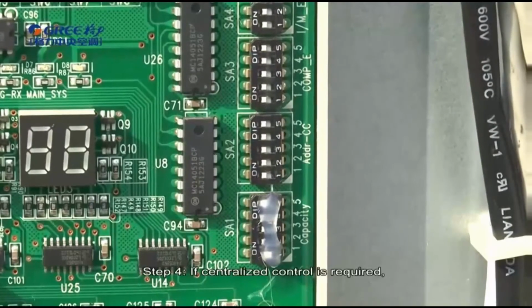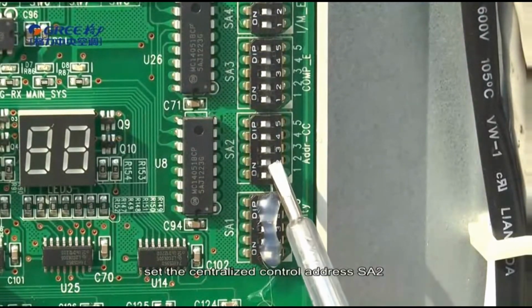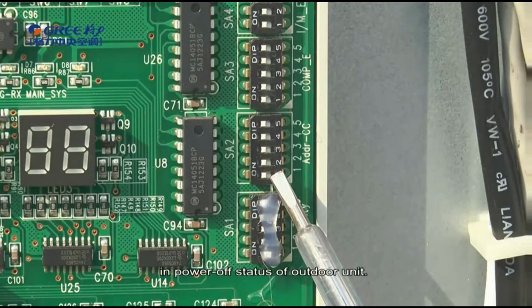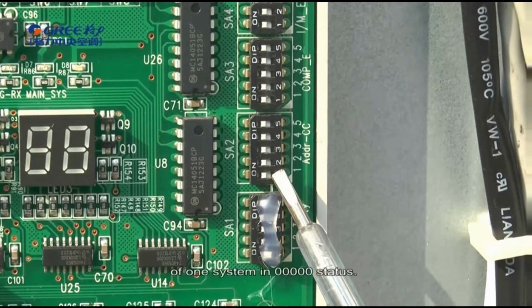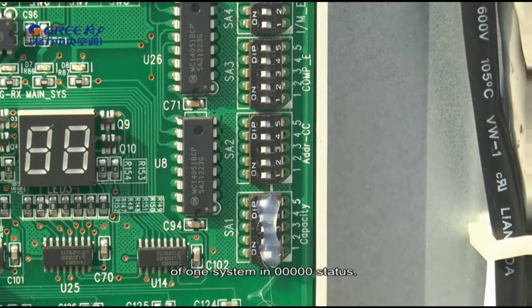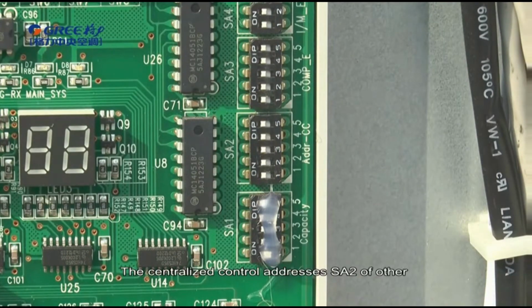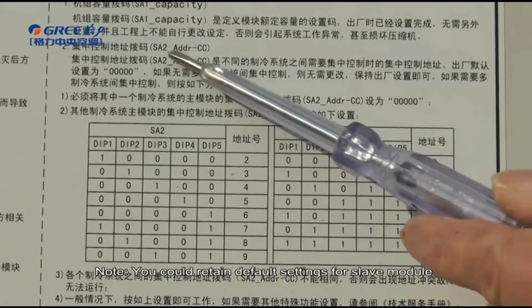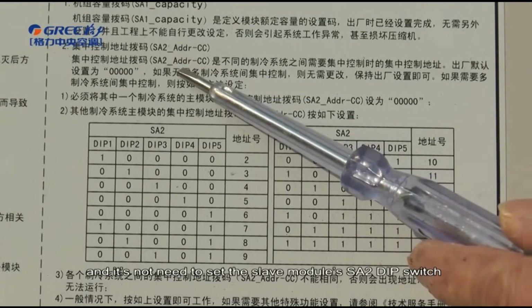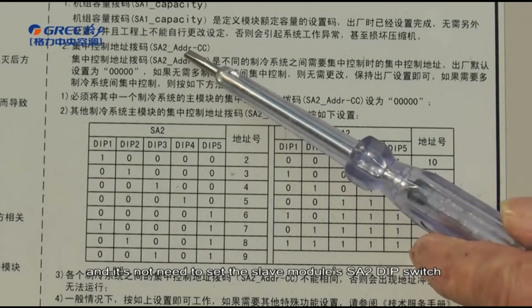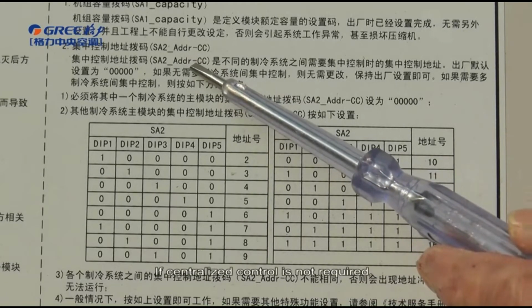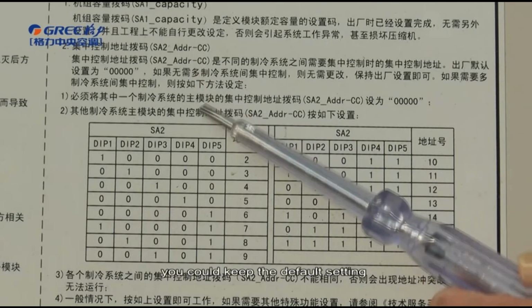If centralized control is required, set the centralized control address SA2 in power off status of the outdoor unit. Retain the master module address setting of one system in 00000 status. The centralized controller addresses SA2 of other systems' master modules cannot repeat. You could retain default settings for slave modules, and it's not needed to set the slave module's SA2 dip switch of all systems. If centralized control is not required, you could keep the default setting, and it's not needed to set the dip switch at all.